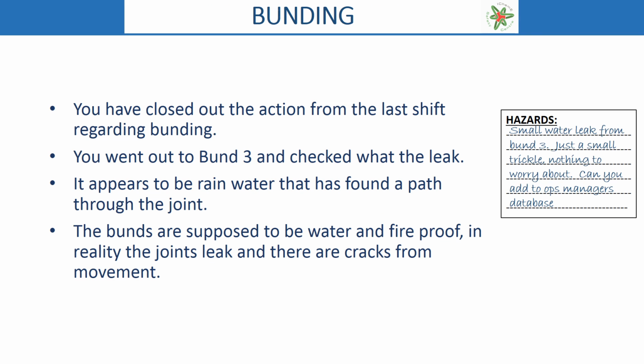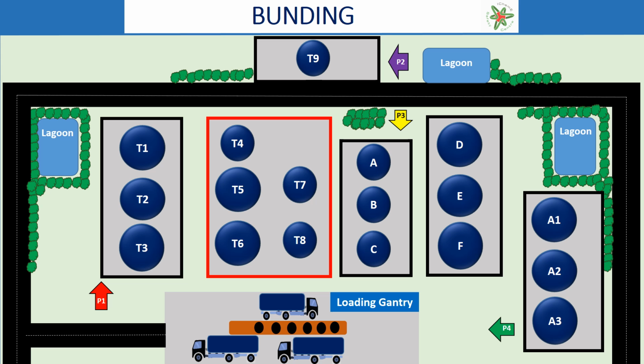We've closed out the action from the last shift regarding the bunding. We've had a look at Bund 3 and investigated the leak. It appears to be rainwater has found a path through one of the joints. The bunds are supposed to be water and fireproof, but in reality some of the joints leak on some of the bunds. There are cracks from movement as well. In the event of a tank leaking, the bund is there to prevent the contents from spreading. Each bund must contain at least the full contents of the largest tank and a safety margin. Bund 3 is shown here, highlighted in red.